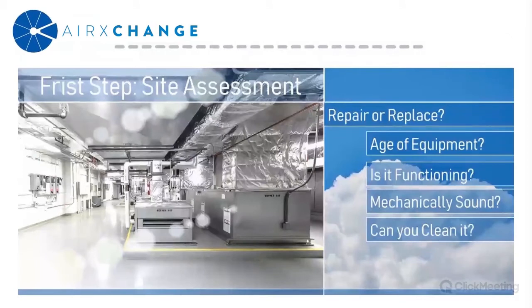Okay, so the first step is to identify whether the component is a good candidate for repair or replacement. So you should be asking yourself right now, what's the general age of the equipment? A properly maintained energy recovery component has a lifespan of usually 15 to 20 years. If the device has never been maintained, it most likely could be substantially less than that, though.